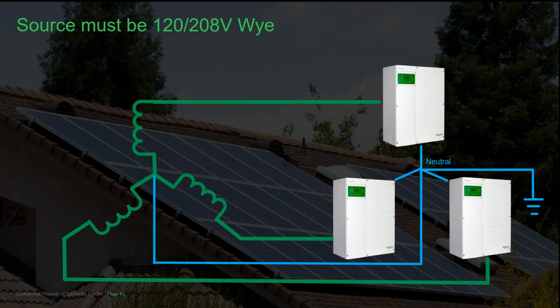Any 3-phase source, whether grid or generator, must have a neutral for a 120/208Y interconnection. With a 3-phase configuration, what you end up with is essentially three 120-volt inverters that are 120 degrees out of phase with each other. This supplies 208 volts from line to line.